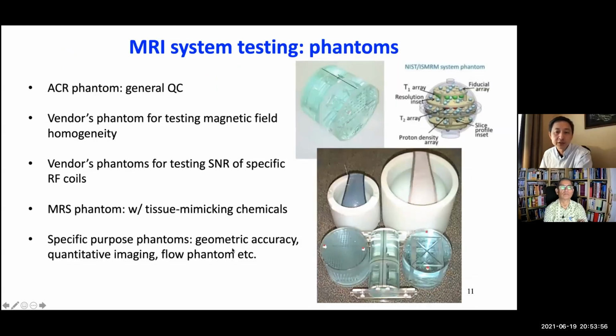For any kind of scanner testing, we will need a phantom to scan. And there are many kinds of phantoms in MRI. Here I just try to make a brief summary. The ACR phantom now is very common in the US. Almost every scanner has an ACR phantom. This is very good for general quality control. So this is the ACR phantom. And in my following talk, I will give examples. For all my examples, I will provide one with the ACR phantom.